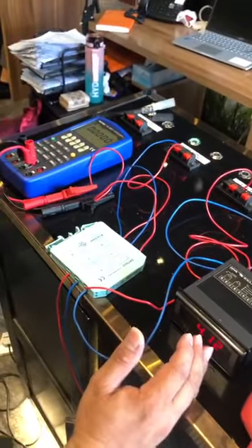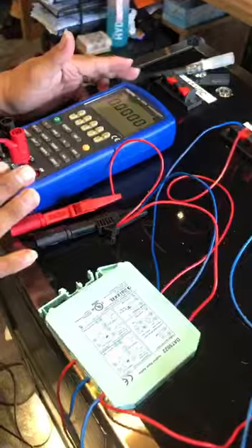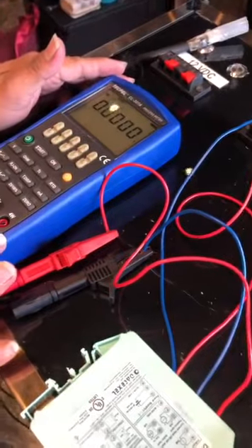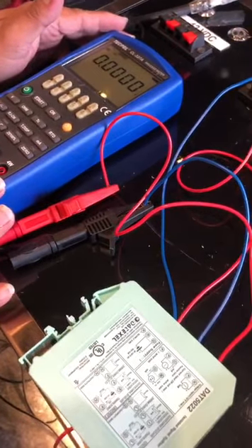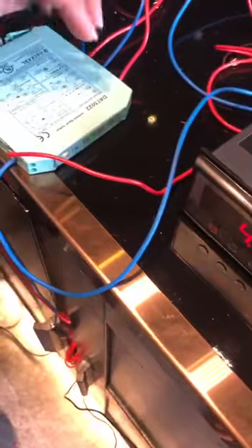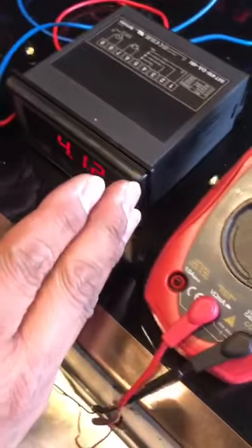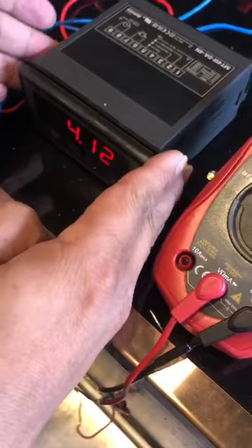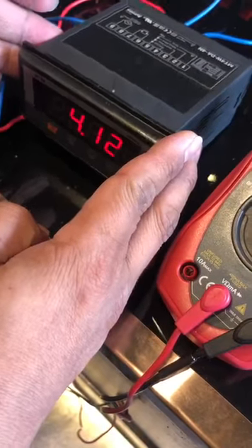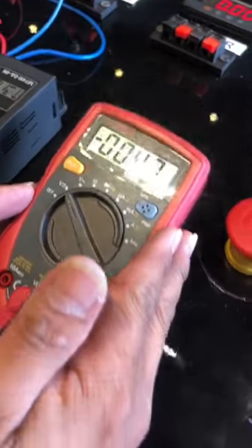One of our signal splitter devices. So, we made some setups here. We have a signal source simulator, which is 0 to 10 volts equivalent. We have our signal splitter, single input. We set this one for 0 to 10 VDC input. And we have output number 1, which we set for 4 to 20 milliamps output, and output number 2, which we set for 0 to 10 VDC output.